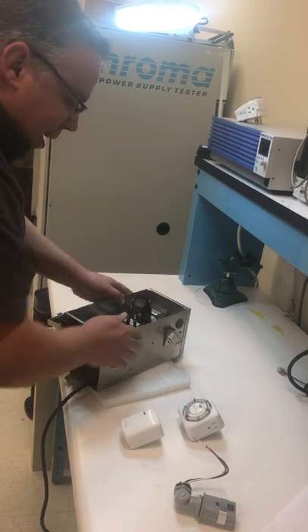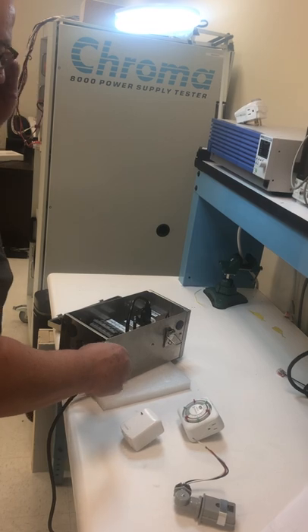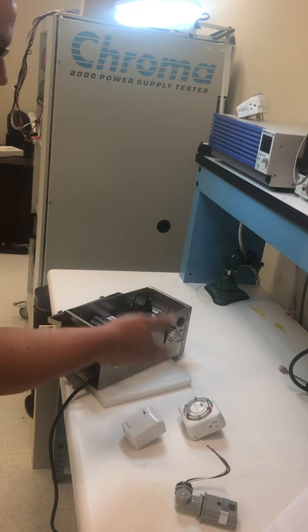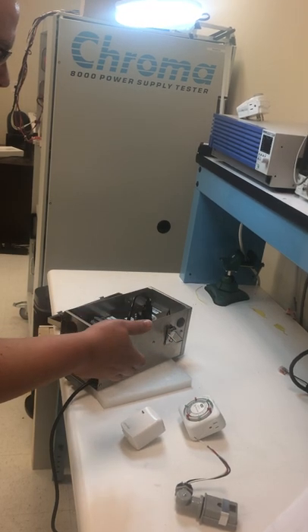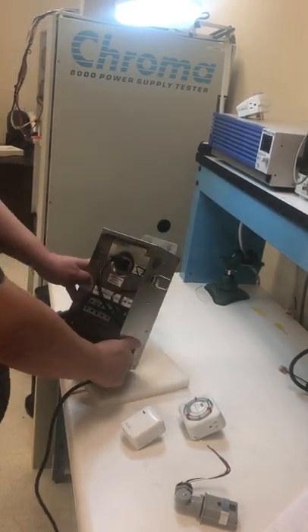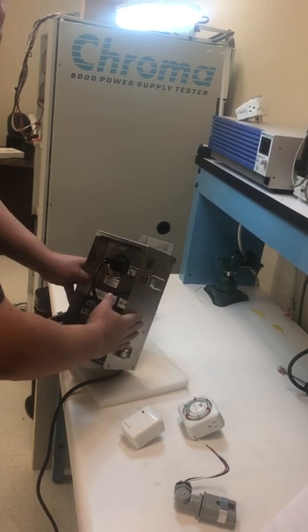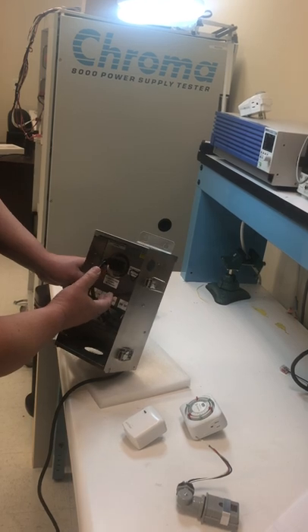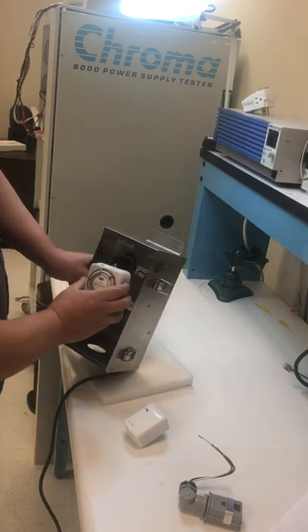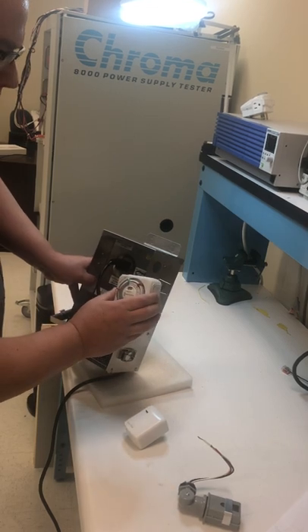This product also supports a wide variety of different controls. We wanted it to be really durable for outdoor use — a lot of products on the market only need a 3R rating, but we went the extra level and certified this for IP65. That keeps dust and moisture out and creates almost an indoor environment inside the box, which lets you use less-expensive indoor-rated controls rather than requiring costly outdoor-rated ones.